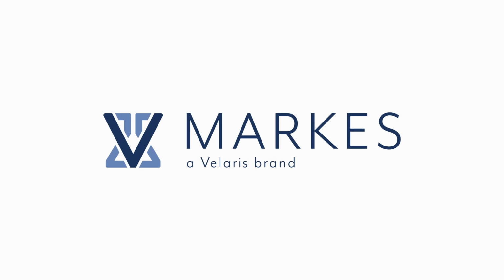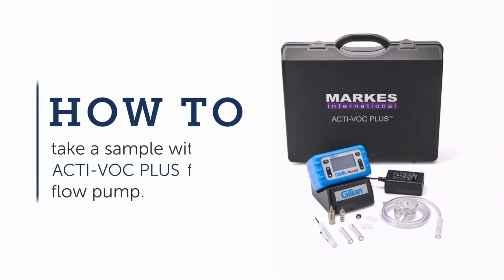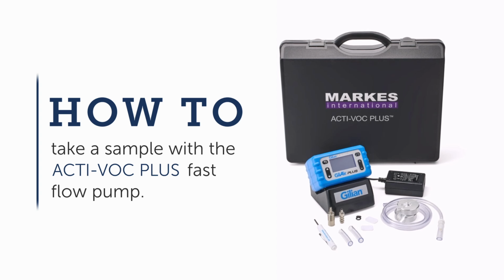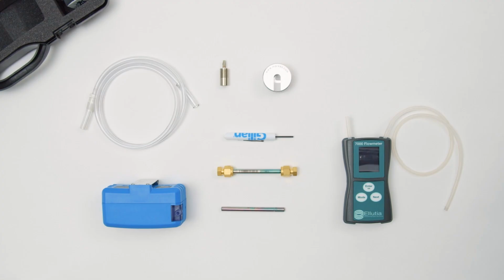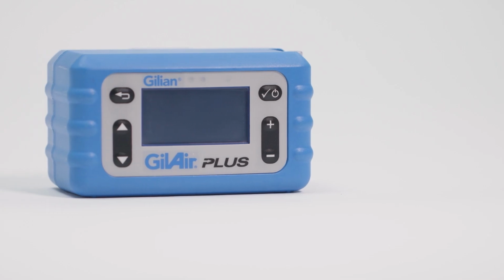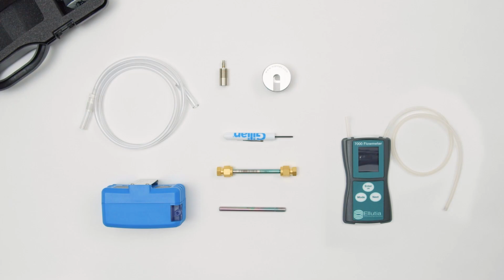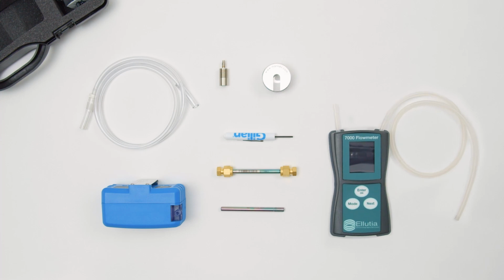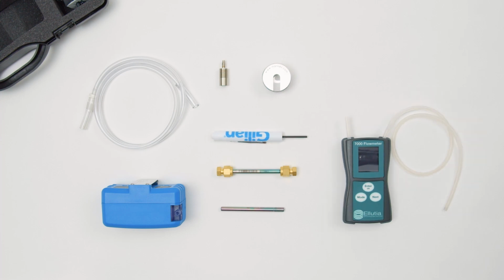The following video will show you how to use the ACTI-VOC PLUS fast flow pump for active sampling onto a sorbent tube. In this video, we will demonstrate how to undertake indoor air monitoring. You will need a fully charged ACTI-VOC PLUS pump, a sorbent tube for calibration, a conditioned sorbent tube with long-term storage caps for sampling, a cap lock tool, a flow meter, and the hex key supplied in the pump's kit.